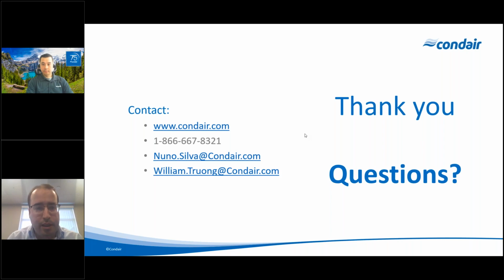How do you control humidity levels during cold nights to prevent condensation? That's a good question - condensation is always one of the topics for humidity. Typically what many people will do, depending a lot on location, is modulate down - set back your humidity when it's very cold outside. They have the temperature outside, and especially with our new equipment, we have IoT, so that's quite easy. Most humidifiers will be connected to BACnet or BMS. So what happens is you typically decrease your set point, or even don't humidify during the night, and before people go to the office or application, you start humidifying. But like I mentioned, if you're in a very cold climate, you might not even be able to do 40% if it's an office.